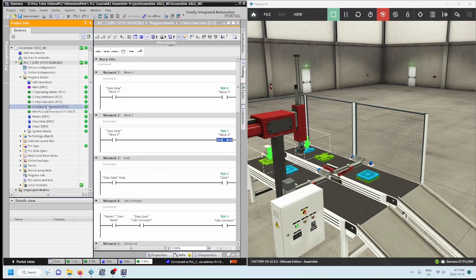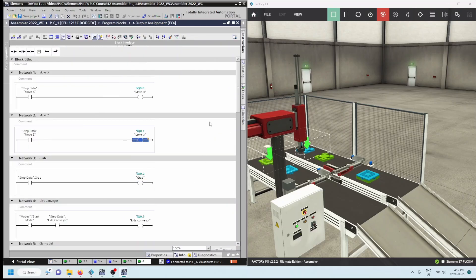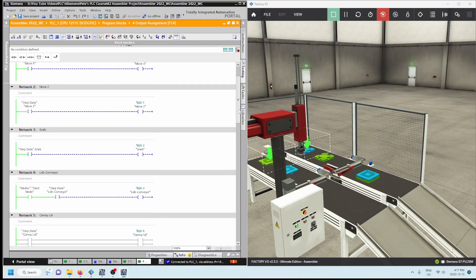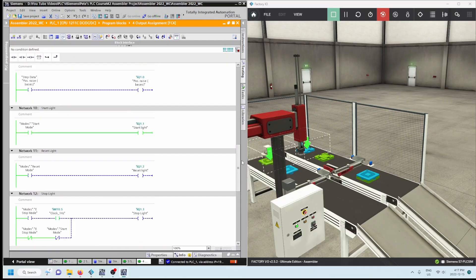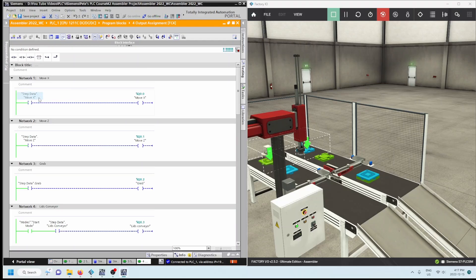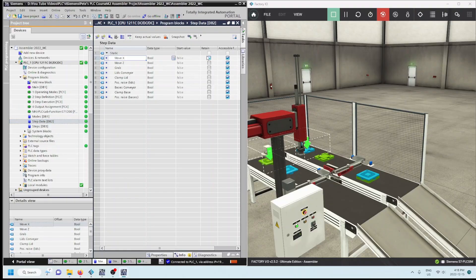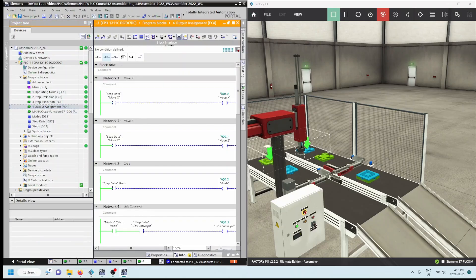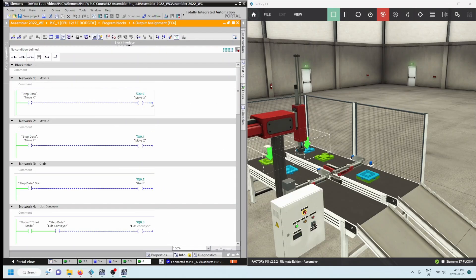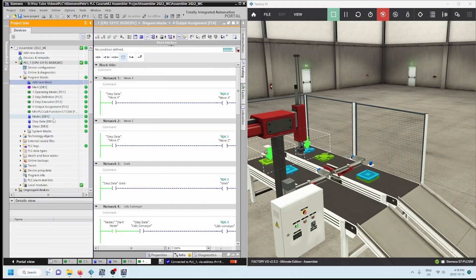Last one: output assignments. This is where we're actually turning on our outputs. I've got all of the outputs that could happen within this scene — move X, move Z. Going to monitor: right now nothing is on. It says if step data 'move X' is true, then I assign that output. Move X is Q0.0. If step data 'move Z' goes true then I turn on Q0.1 for move Z.